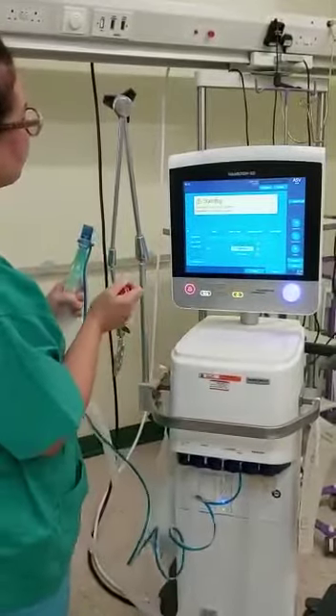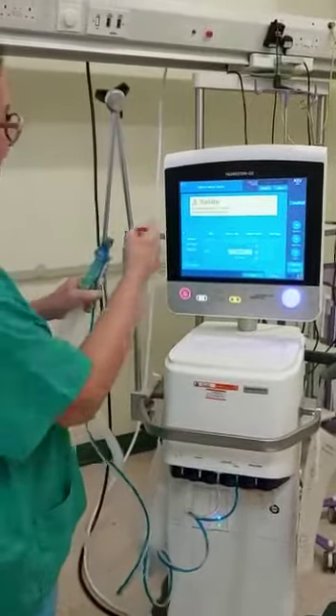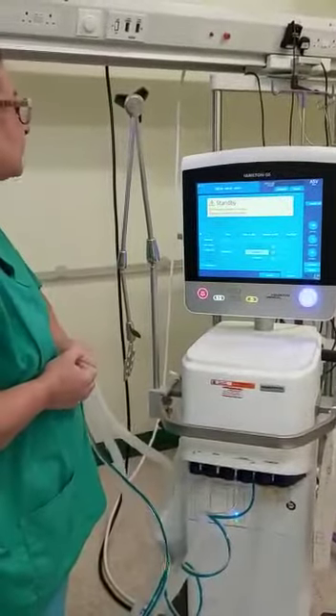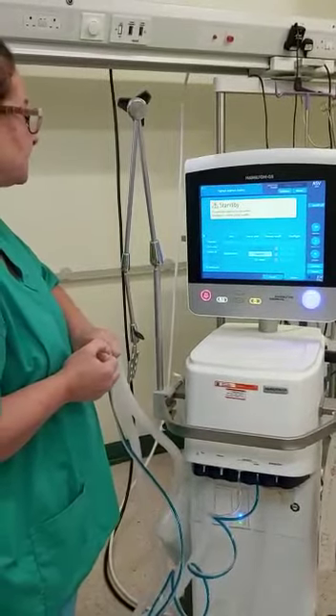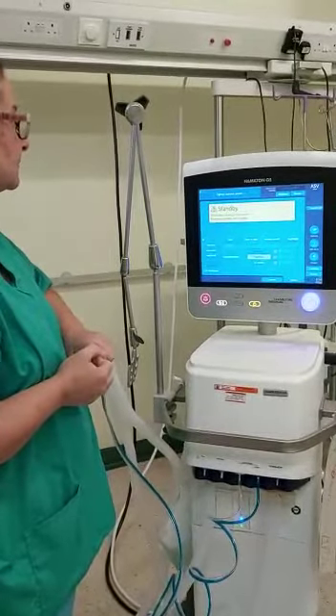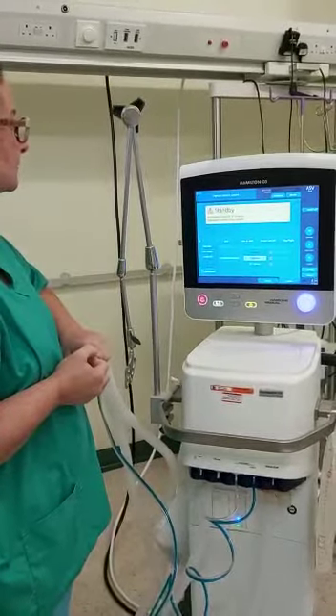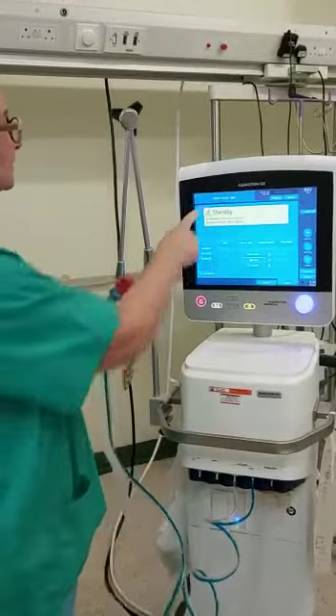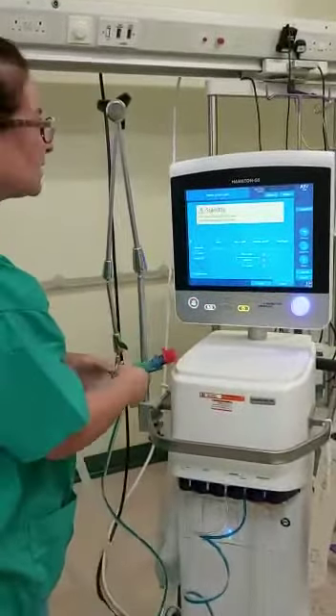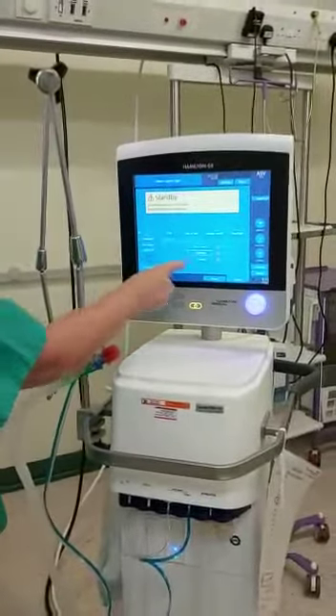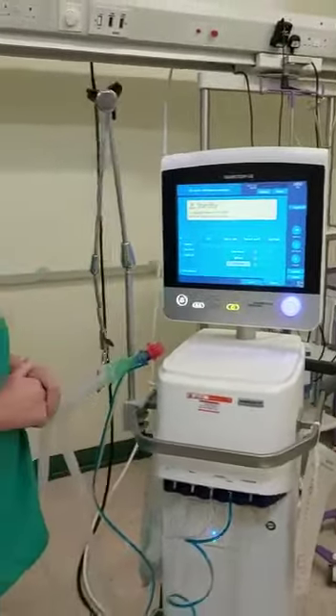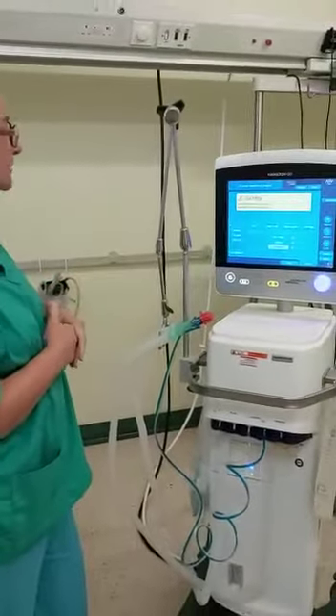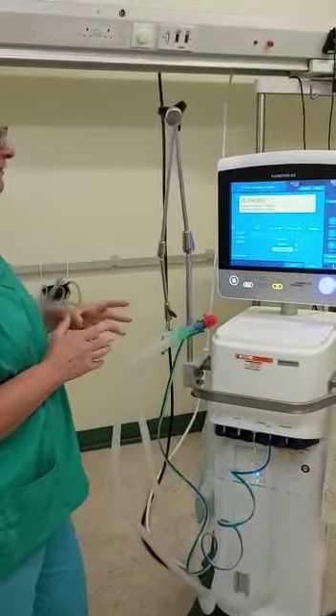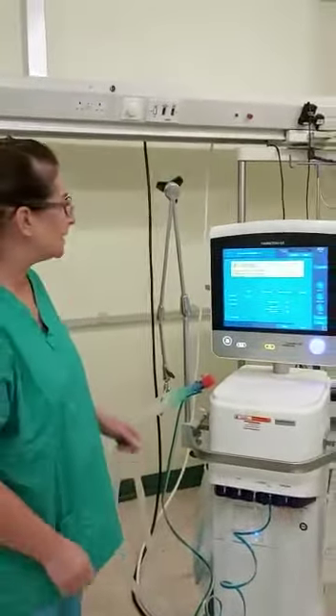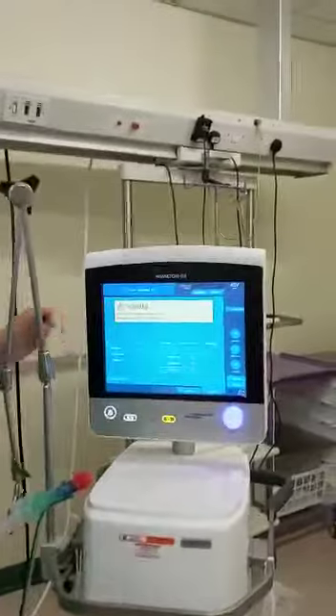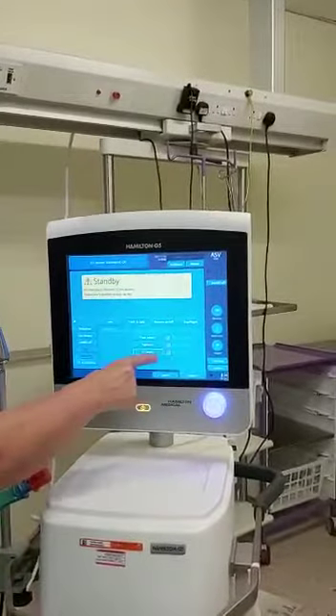So tightness, it's going to tell me to tighten the patient's system in a minute. So click the red cap on the end and press quite hard. Patient system tight, so that means that that's passed, and again it's updated with the date and time. And then the final one is the oxygen sensor, which you can just click on. It'll just calibrate itself without you having to do any intervention. So that's our final calibration. Oxygen sensor is calibrated okay, and again it's updated here.